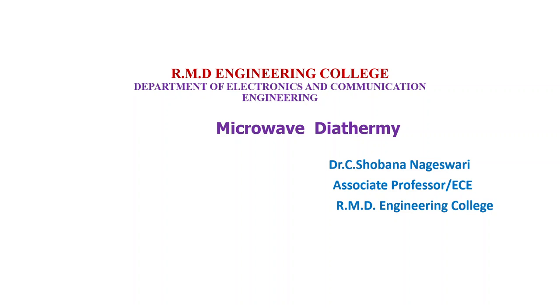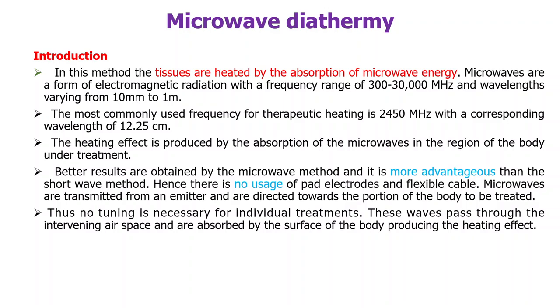Good morning. In this video we are going to discuss about microwave diathermy. In the earlier session we have discussed about shortwave diathermy. The second type of diathermy is microwave. The microwave energy is absorbed by the human body and that produces the heat. The range of microwaves we are using is usually 300 to 30,000 MHz and the wavelength ranges from 10mm to 1m. The most usable range for therapeutic heating is 2450 MHz and the wavelength is 12.25 cm.